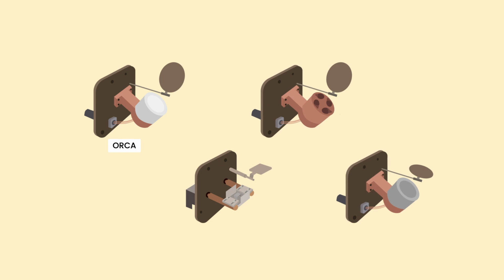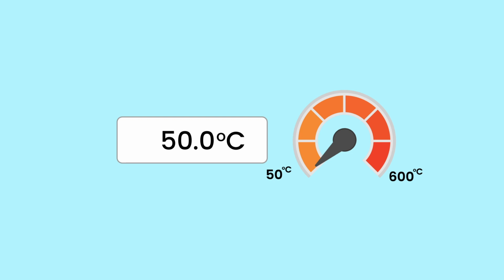Versatility is key in thin film deposition, and the Orca works well with other sources. It can be used in conjunction with sputter sources, e-beam sources, thermal sources, and more. If you need a system to carry out low temperature evaporation between 50 and 600 degrees Celsius, with control to 0.5 degrees, then our Orca organic evaporation system at Korvus Technology is a great option.